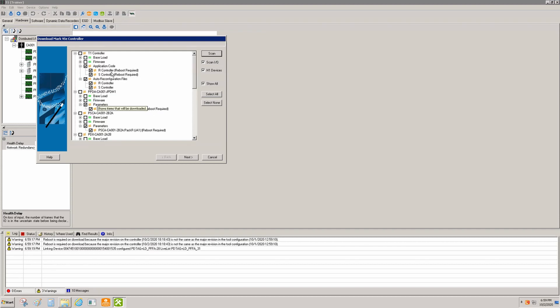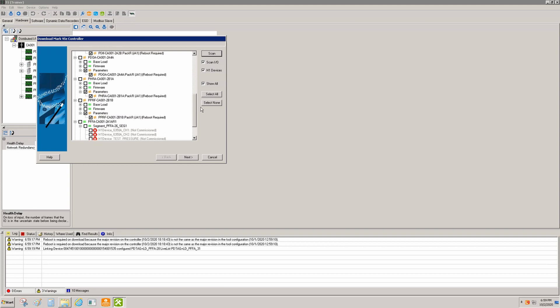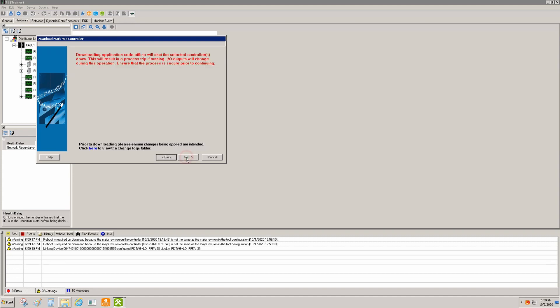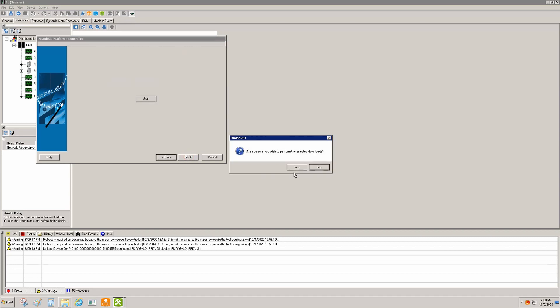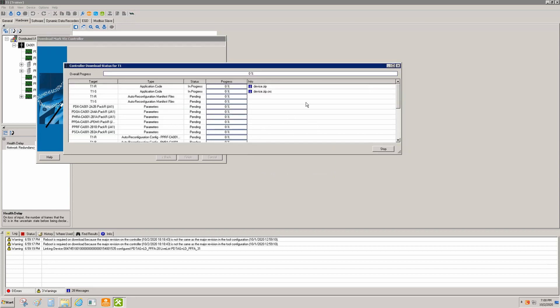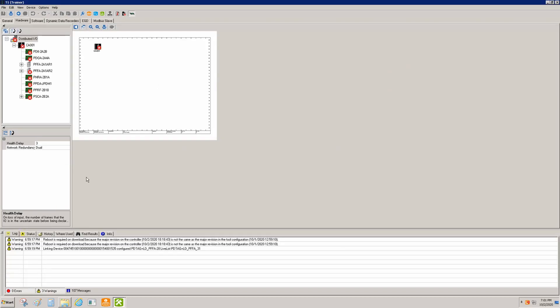It's going to warn us in several places that a reboot is required. First, the warnings say we have to reboot because the major revision on the controller doesn't match the one in the configuration. The download box also warns that it's going to reboot, and you'll see almost every card will have to get its parameters and reboot to sync back up — with the exception of the PFFAs, which won't accept anything right now. It's going to warn us again that this will shut down the selected controllers. We always want to pay attention to all these warnings even though they seem repetitious. It knows we're rebooting so it's going to download to both controllers at the same time.